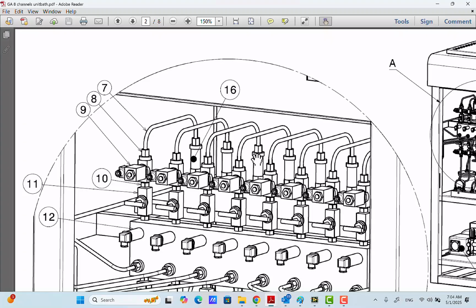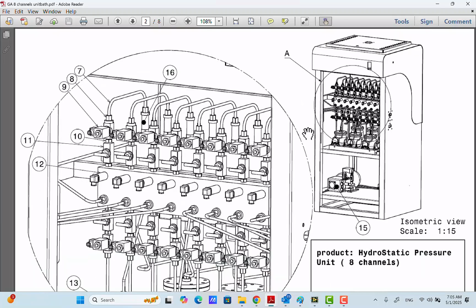For cleaning of the check valves, you need to open the connections on two sides of the check valve, and you will see inside it an Allen type of screw. You will open that screw, and inside these check valves, you will have a ball and a spring. In case of solid objects coming into the water inside the unit, you can remove those solid parts or dirt that come into the line, and the check valve will function properly.